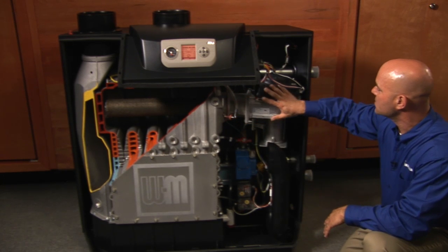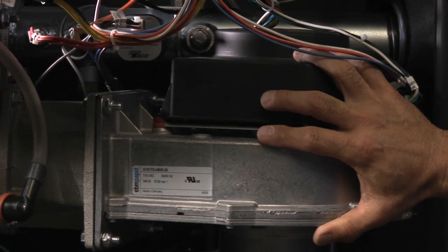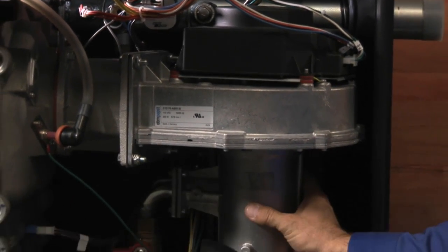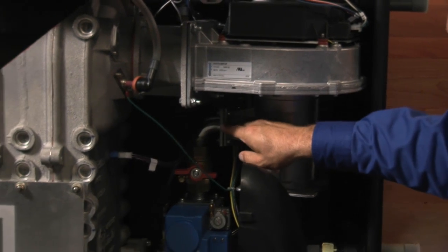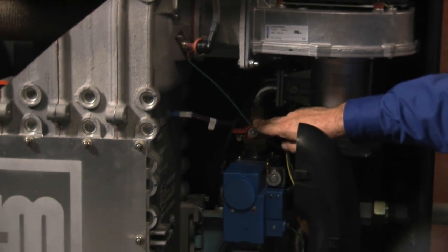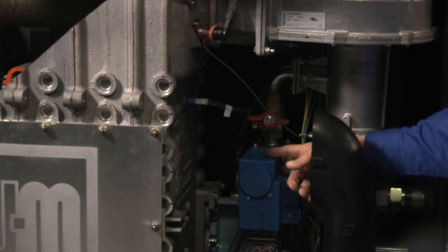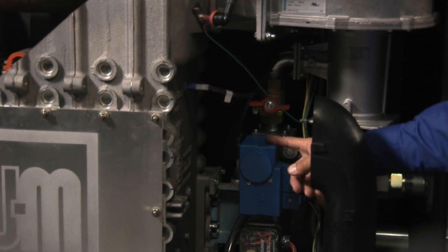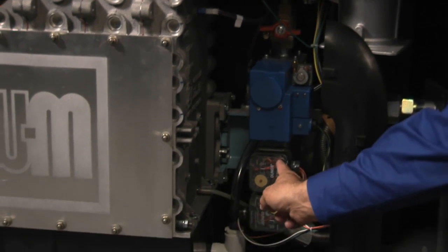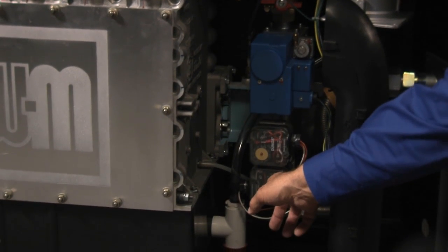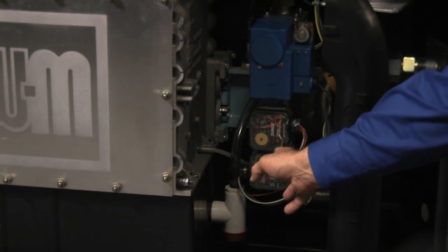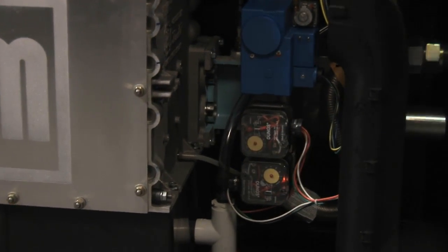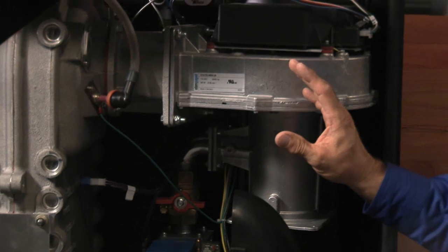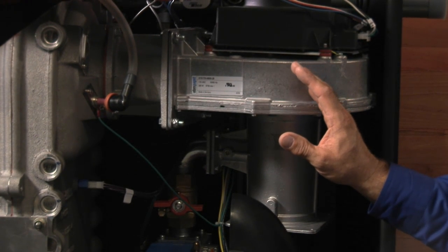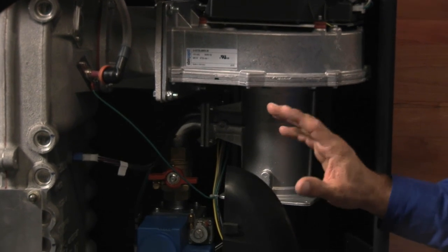Back up to the top, this is our combustion blower. And the combustion blower is hooked to a venturi. The venturi is then tied into, comes down around this elbow. There's a shutoff valve. It goes into a 120 volt gas valve. And then just below that we have a high pressure gas switch and a low pressure gas switch. And the reason we have the high and low pressure gas switches here and the low water cutoff on the boiler is that it meets CSD-1 standards, CSD-1 compliant right out of the box, which will save a ton of time on labor on the install.